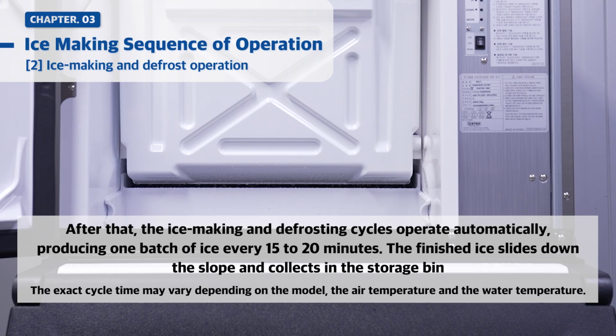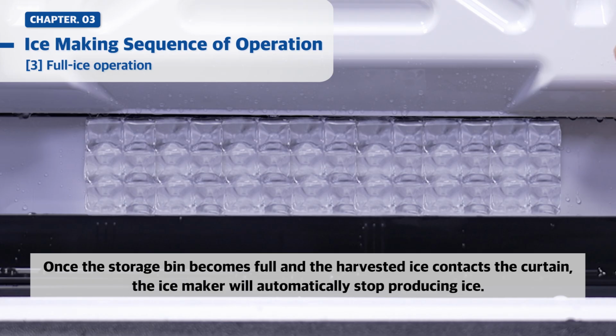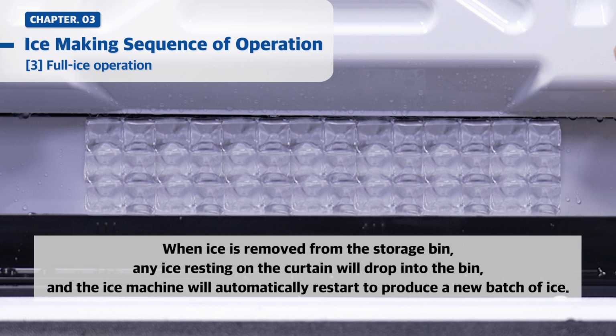The finished ice slides down the slope and collects in the storage bin. Once the storage bin becomes full and the harvested ice contacts the curtain, the ice maker will automatically stop producing ice. When ice is removed from the storage bin, any ice resting on the curtain will drop into the bin, and the ice machine will automatically restart to produce a new batch of ice.